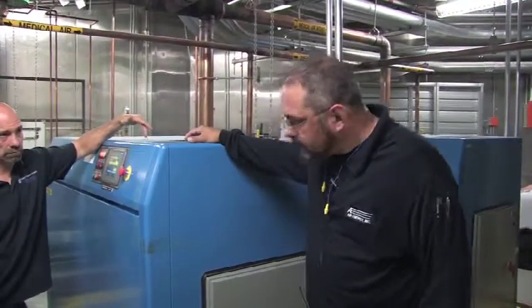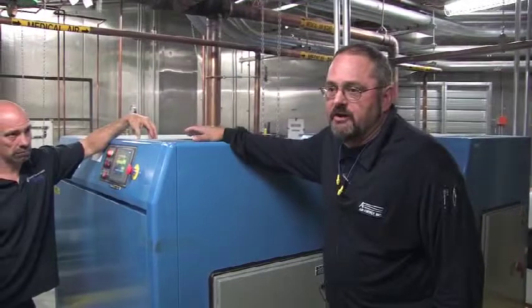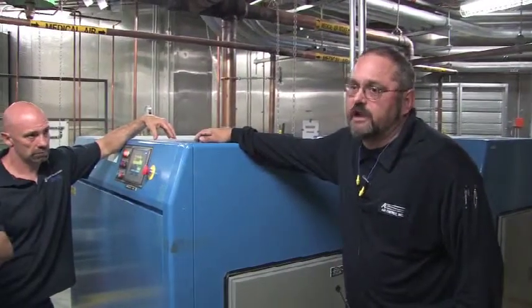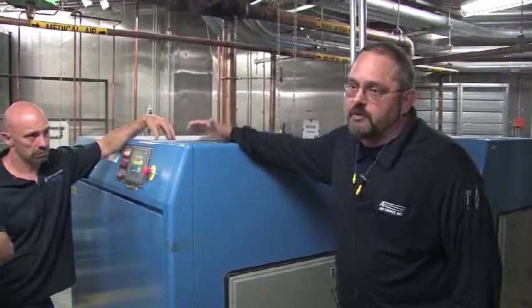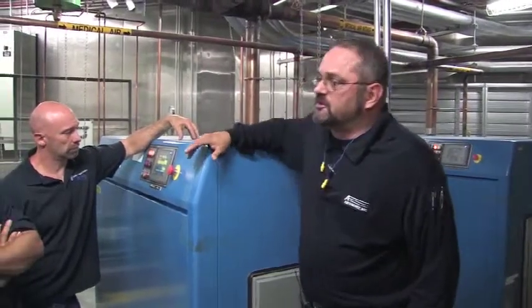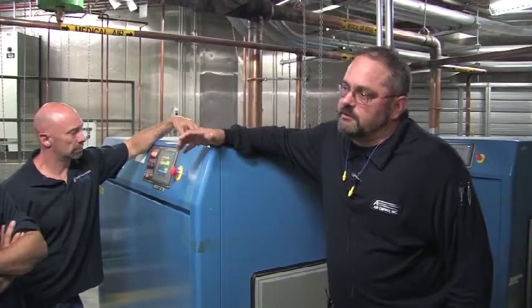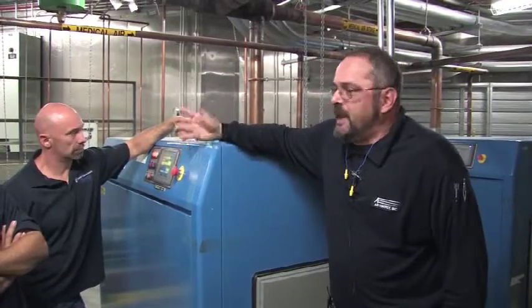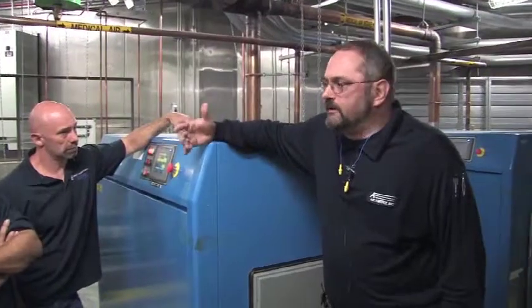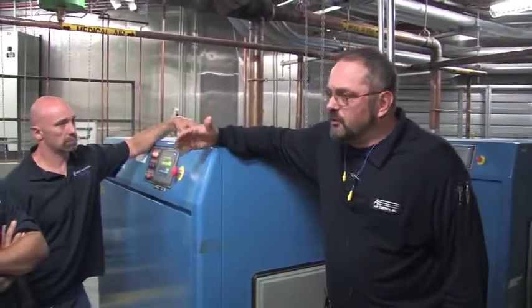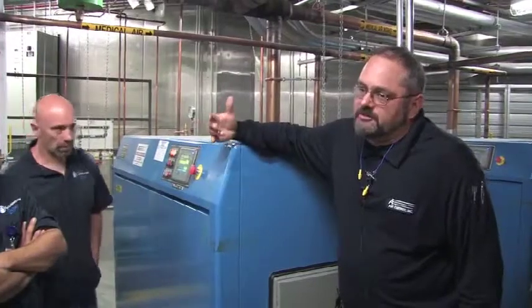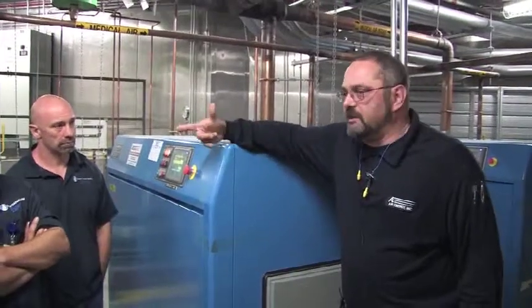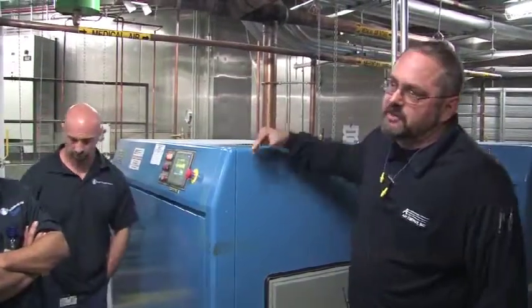The other difference between most of the other systems you have, if I remember right, Larry, are duplex systems. A lot of them are all 2 compressors. And the way the duplex systems alternate is basically there's no interconnection between the machines. You just program them identically with 2 different pressure set points, and you tell one it's the lead machine, one it's the lag, and either every day or once a week, whatever you program it to at a certain time, as long as the clocks are within a minute or so of each other, whichever one's in lead switches to lag, the one that's in lag switches to lead.